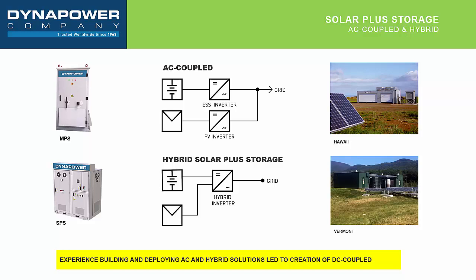The second topology, which is considerably less common but still has a number of installations in the field, is the hybrid solar plus storage topology. In the hybrid topology, you basically have one inverter, a single inverter with multiple DC inputs, at least one for solar and at least one for storage. So you have one box, one set of controls, and a single AC interface. So there's an intuitive value and benefit here to having a single box.